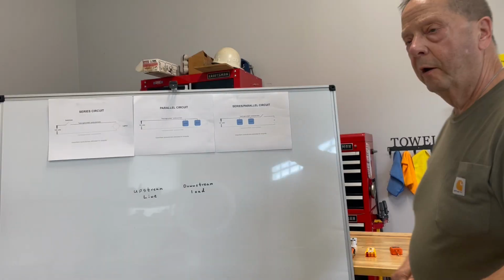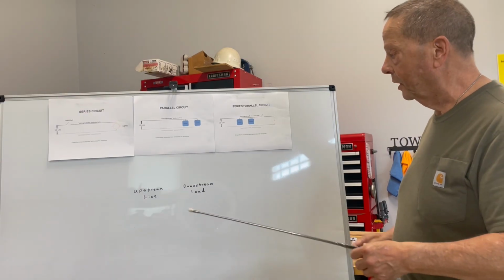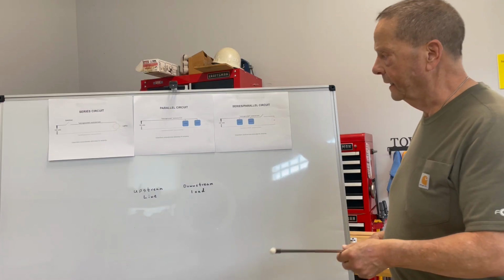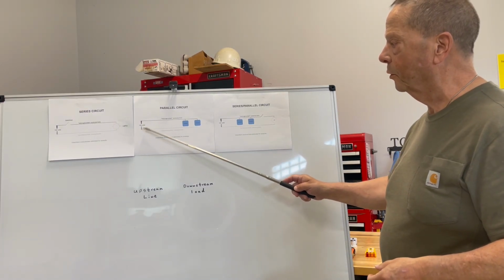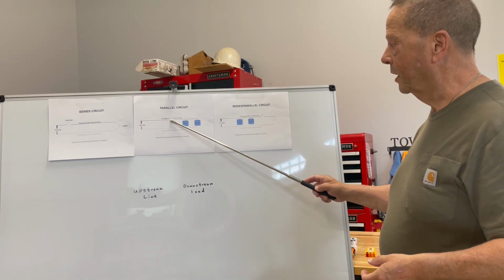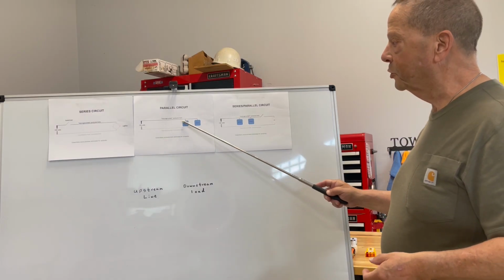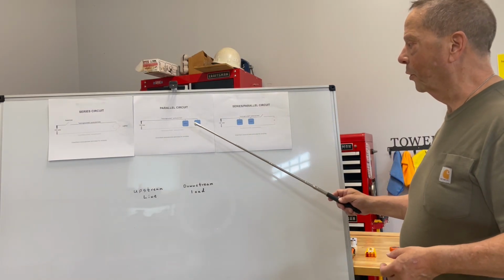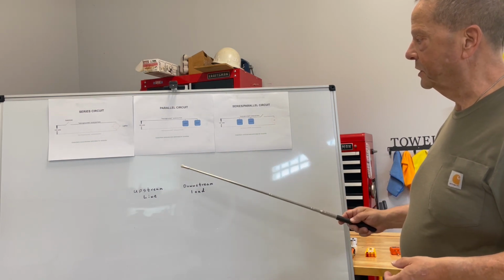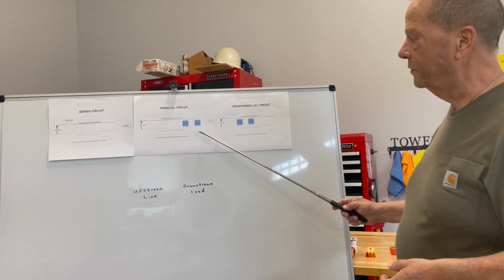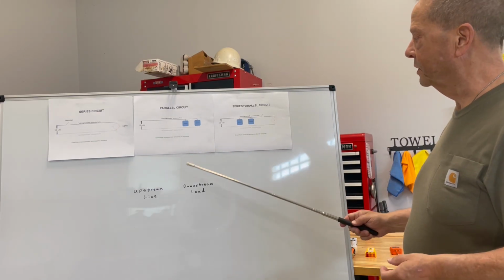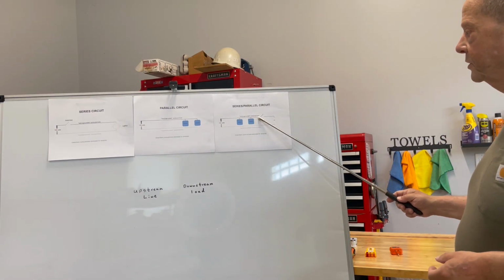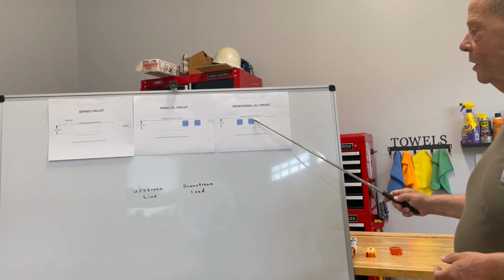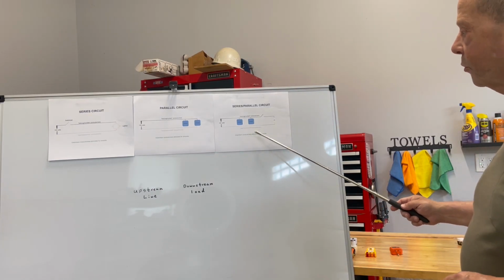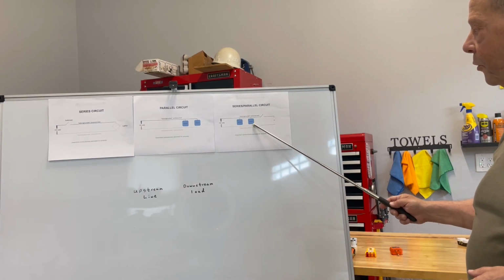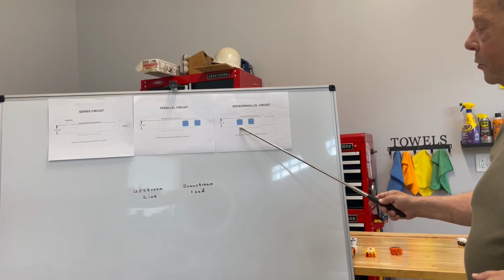Okay, I introduced a new set of terminology to you, upstream and downstream. And what I mean by that is if you have a circuit here, here's your 120 volts, which could be probably the circuit breaker. And as we come down here, these two receptacles are downstream of the circuit breaker. And furthermore, this receptacle is downstream of that receptacle. This receptacle here is upstream of that receptacle, as you can see the way the voltage flows. And here, this switch and light are downstream of these two receptacles here. So if you had a problem where there was a loose connection in, say, this receptacle, the problem could be in that box, or it could be in the receptacle that is upstream.